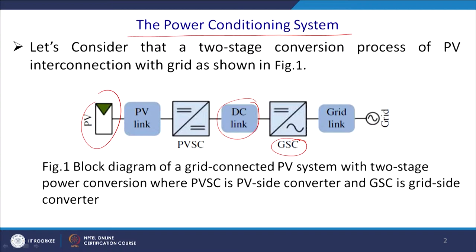From the DC link there may be pre-processing to obtain the DC bus voltage. You have a grid-connected inverter and a grid link — essentially a PWM inverter — and for this reason it will inject high-frequency harmonics. To bring that harmonics level down to a desirable level, you have a filter, which is essentially your grid link. This is the two-stage conversion of the PV interconnection with the grid as shown in the figure.